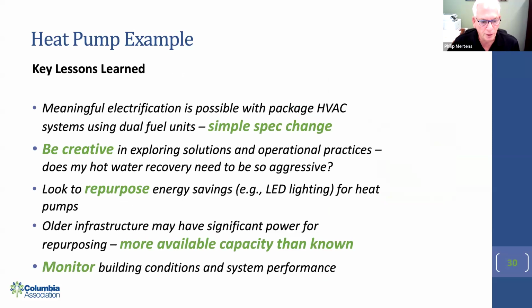Next slide, please. Key lessons learned. So meaningful electrification is possible with package HVAC systems using dual fuel units. And that's a simple change. It's just deciding that instead of your standard RTU, you utilize the heat pump technology. And you need to be creative in exploring solutions and operational practices. This is right sizing systems. Does your hot water need to be so aggressive?